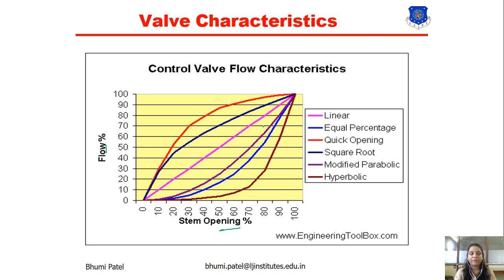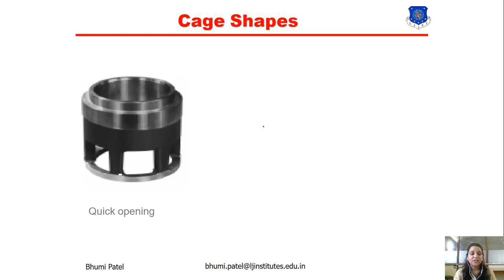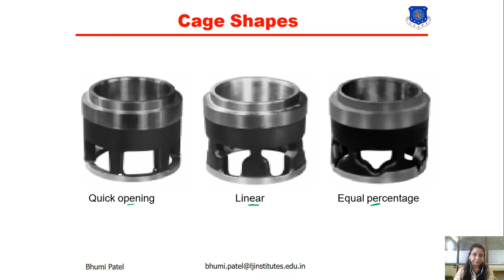Now with different cage shapes, the characteristic will be different. Here three types of cage shape are given. First one is the quick opening, second is for the linear, and the third one is the equal percentage. If we want equal percentage output, we can connect the cage in the control valve in this shape. If we want linear characteristic, we can connect the cage in this shape, and if we want quick opening, we can connect the cage in this shape.